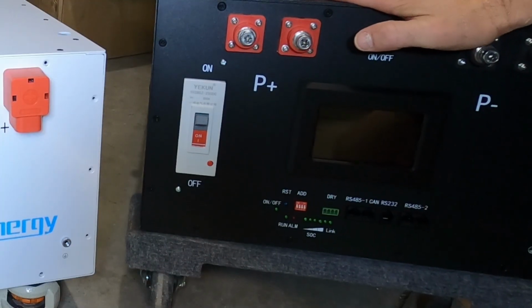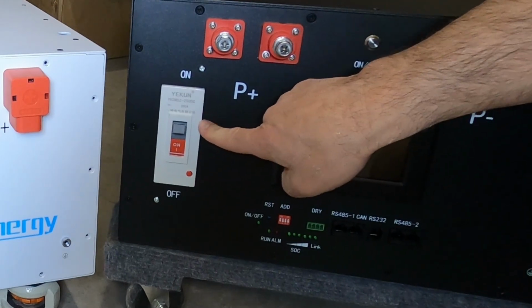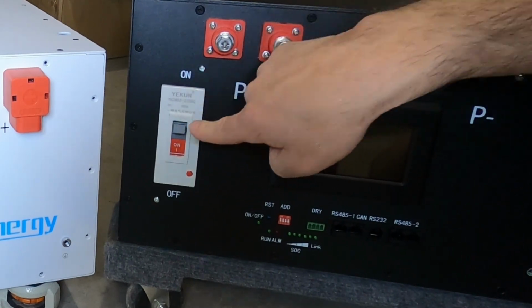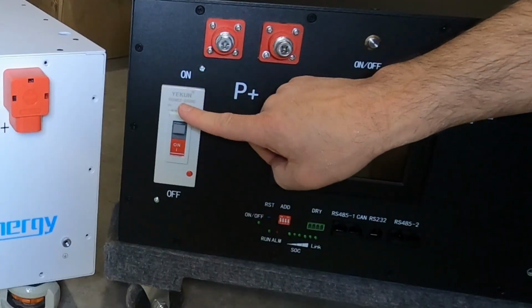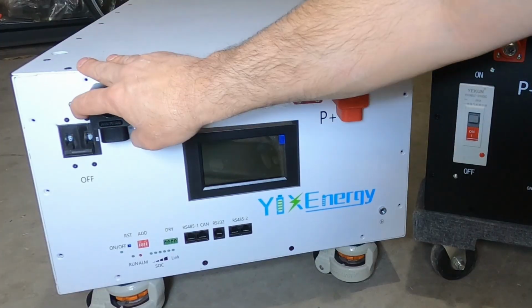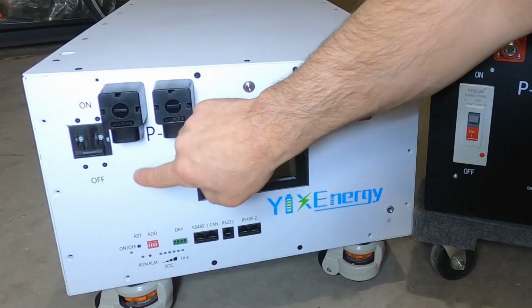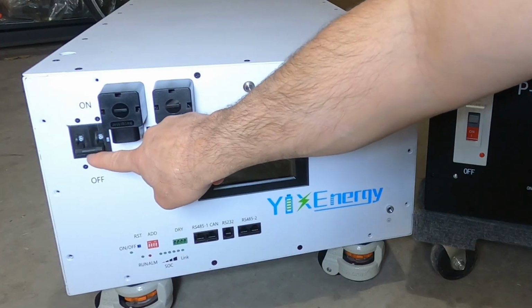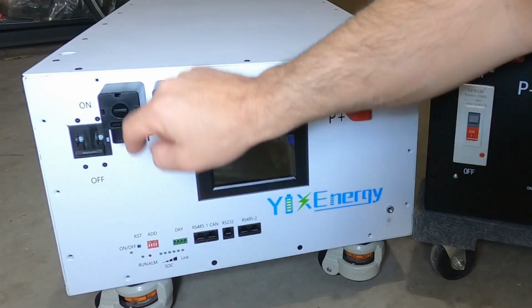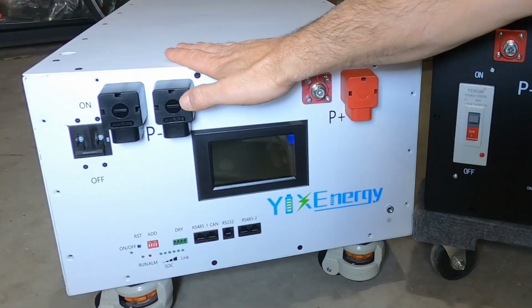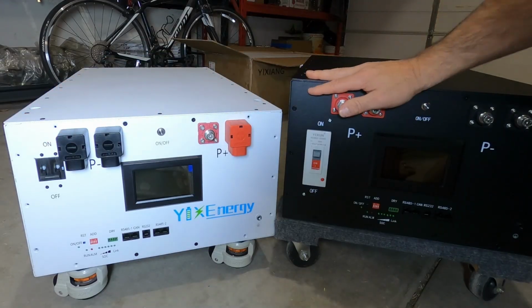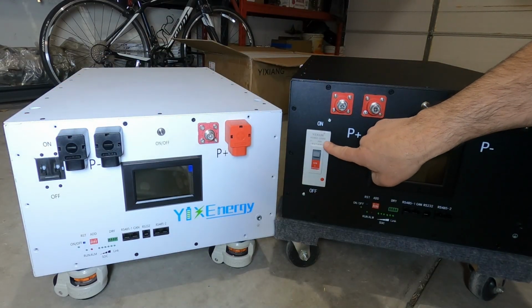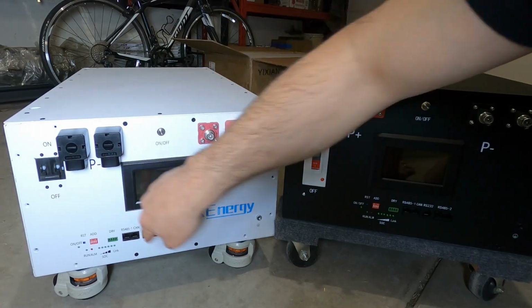Moving on to the circuit breaker, you'll notice this huge 250 amp DC rated bidirectional circuit breaker. That's important, we'll cover that later. Over here on the version 1 box, we got this little rinky-dink 220 amp switch breaker. Does work though, I have tested it in the previous video. But the main issue is this is 250 amp rated and this is 220 amp rated.